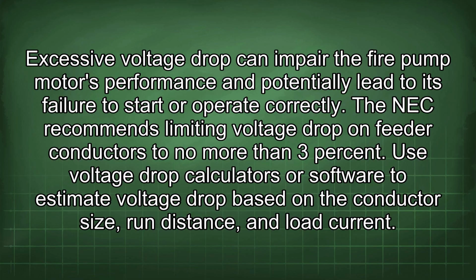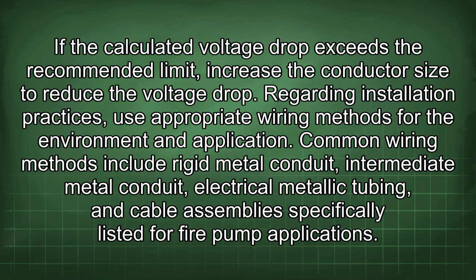Use voltage drop calculators or software to estimate voltage drop based on the conductor size, run distance, and load current. If the calculated voltage drop exceeds the recommended limit, increase the conductor size to reduce the voltage drop. Regarding installation practices, use appropriate wiring methods for the environment and application.